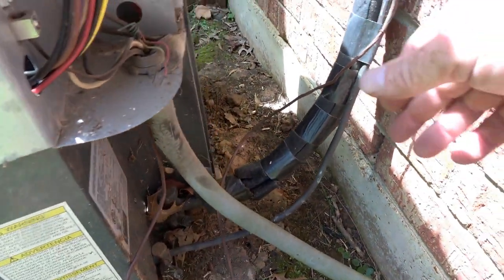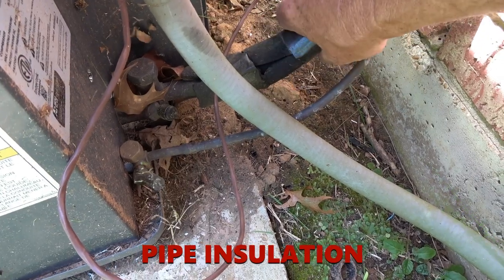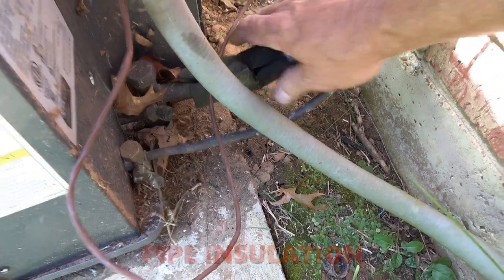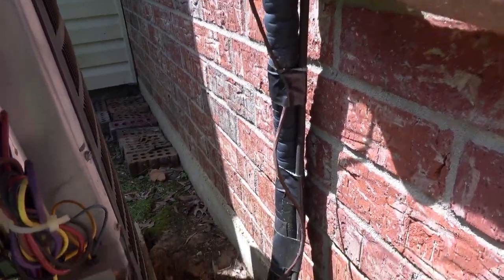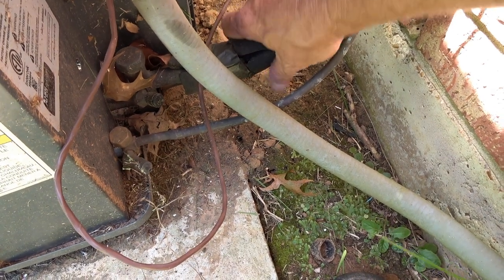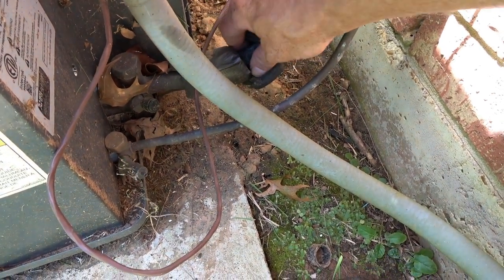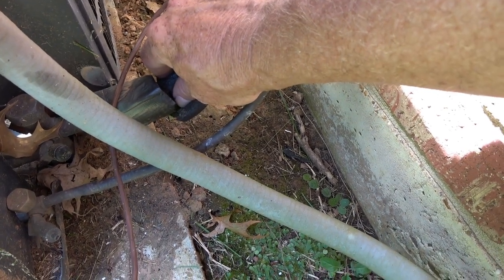While we're down here, this Rubatex insulation keeps the suction line from warming up too much and prevents condensation. While doing maintenance on your condenser, check this line set to make sure it's in good shape — it does weather and deteriorate over the years. Residential suction line sizes are typically five-eighths, three-quarter, seven-eighths, or one and one-eighth inch — those are the four sizes you'll generally see.